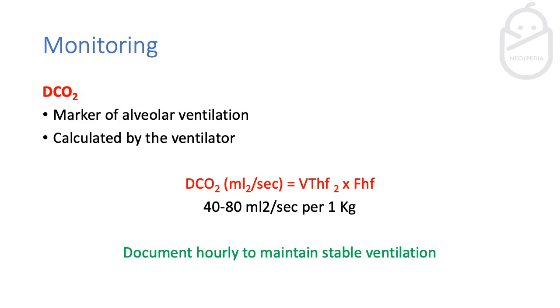Another monitoring parameter is the DCO2, which reflects how effectively you're ventilating the alveoli. It's calculated by the ventilator automatically. You need to ensure it runs between 40 to 80 mL²/second per kilogram — so for a 2 kg baby, the target range would be 80 to 160. Nurses should document this hourly to ensure stable ventilation is being maintained.